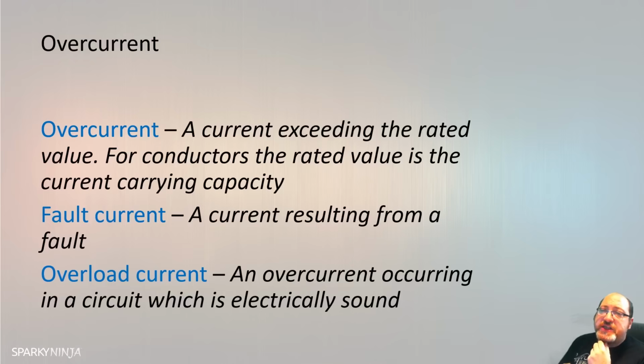But if I was to say to you a cable can carry 27 amp when it's installed in the reference method of surface clipped direct, and you chose to put that on a circuit protected by a 32 amp breaker, then technically that 32 amp breaker is not protecting that cable from overload if overload was to occur. But overcurrent is the current going over the rating of the cable.